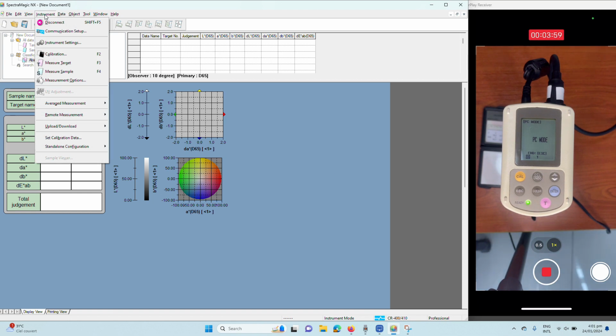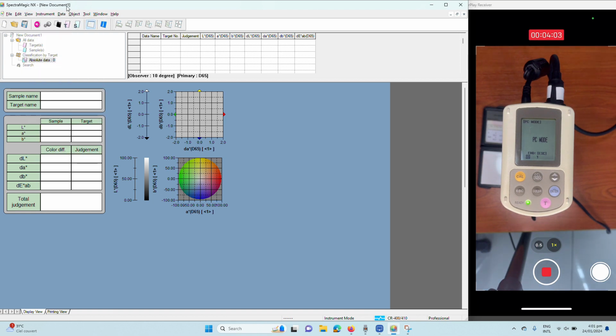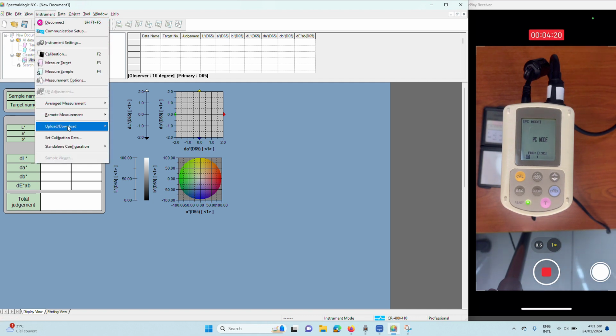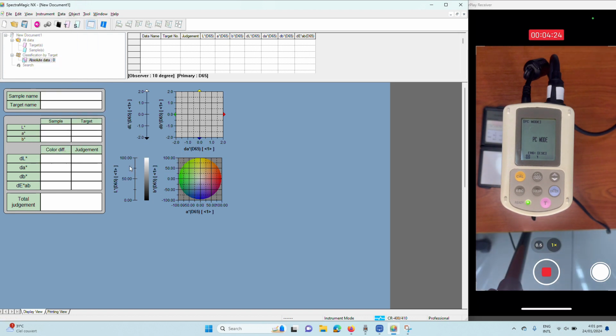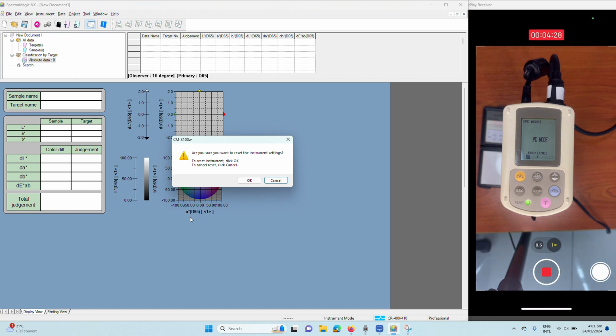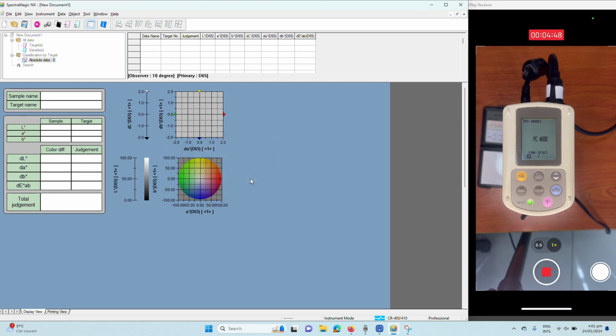And now, first of all, initially you have to set up your illuminant and observer. Now, here's the thing about the CR400. The CR400 can only use the 2-degree observer, so you might want to change that. But the best way to do it is to go to standalone configuration and initialize instrument. This way you can reset your instrument. Let's say someone has been using it before, unless you are the same person who is using it, so it's not much of a problem. But if you don't know who was using it before, perhaps you want to reset it. This is how you do it. You just reset the equipment, and now it's reset. I don't know if you noticed, but it was D65 earlier. Now it's C. So the initial condition of this equipment is actually C, and the observer is 2 degree.